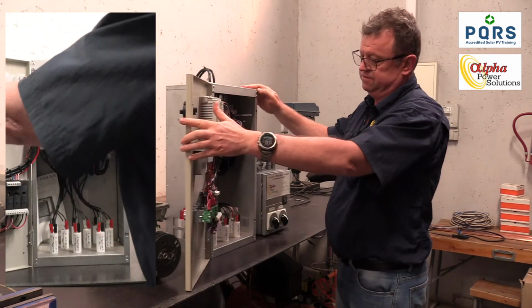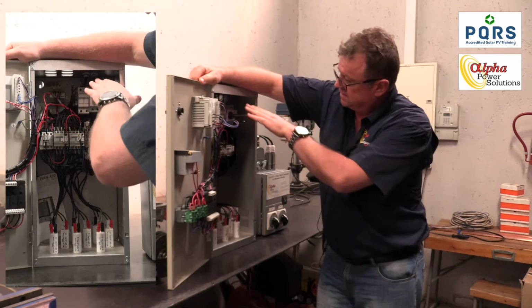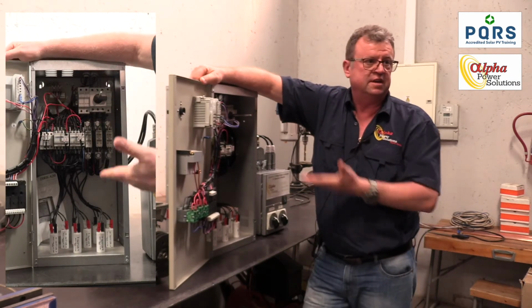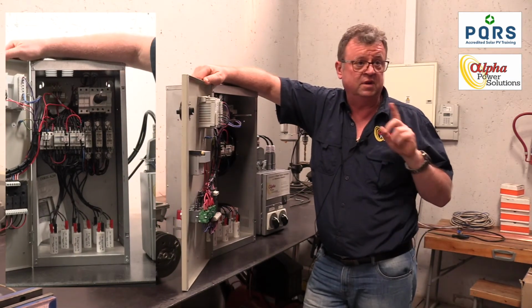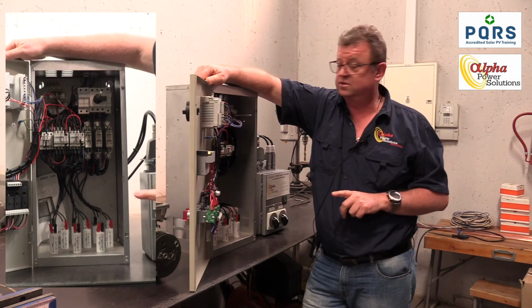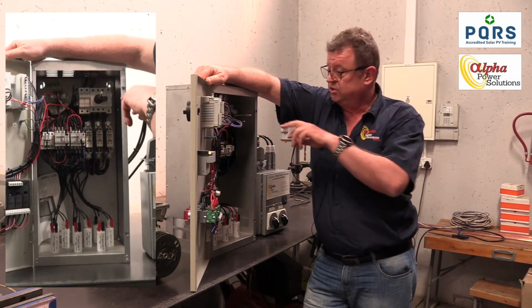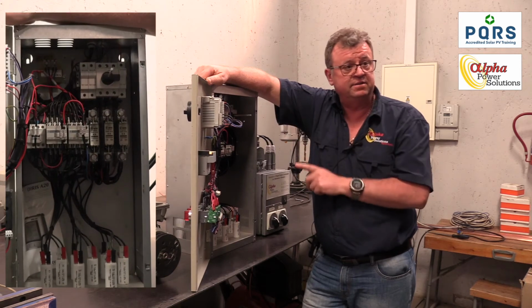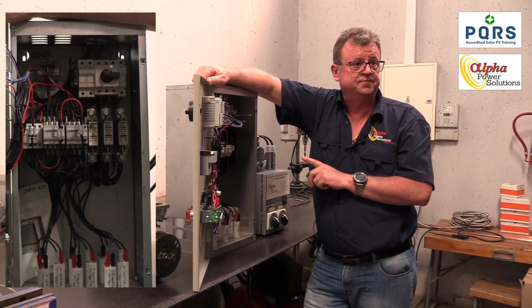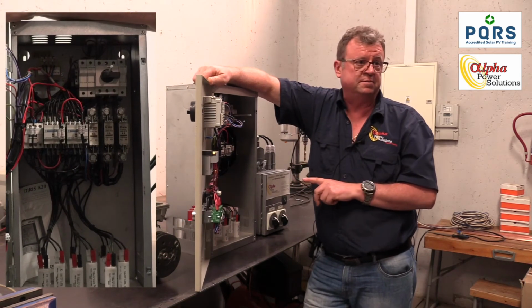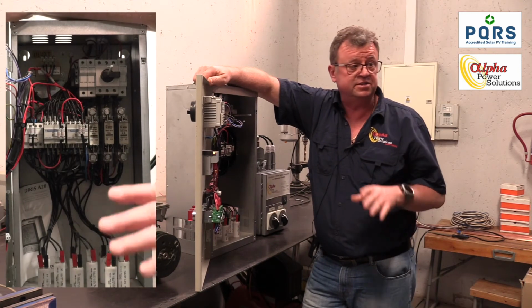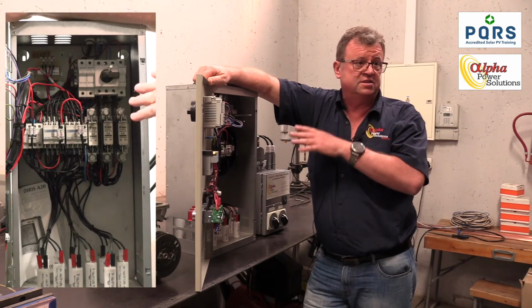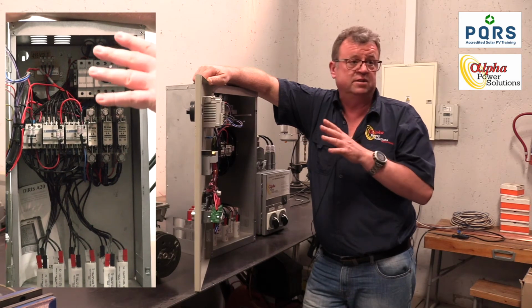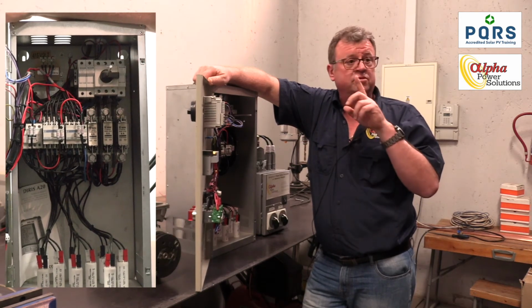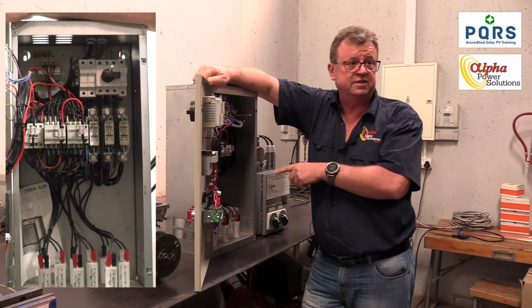So what you have here is basically an isolator to isolate the incoming power. Remember, one thing is that when you install a power factor correction system, you cannot connect this directly onto the main bus bars. This must always be protected by a circuit breaker. We see many installations where this stuff is installed directly on the bus bar.